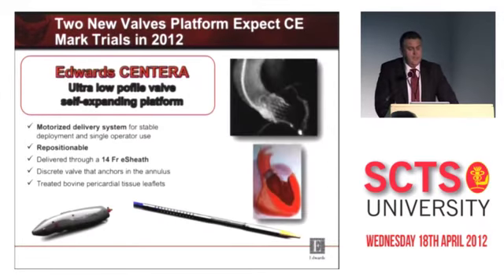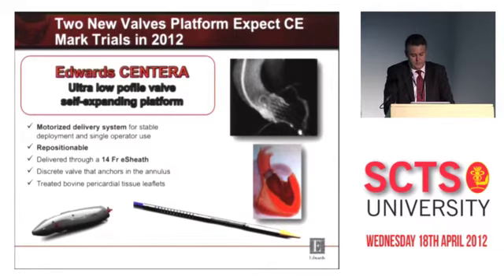The second valve is the Edwards CENTERA. The first in man has been done recently. And this valve is already a project that was in development for 10 years in Edwards. What we would like to come with is a motorized delivery system for stable deployment and single operator use. It will be a repositionable device, delivered through a 14 French sheath. It will be, again, discrete and much more size options than what is on the market today. And we would like to continue to have this treated as well with bovine pericardial tissue leaflets.